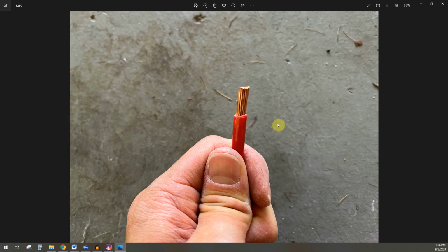And the reason for this is that if you need to take out the wiring later and need to bend it, and you have nicks on the wire, there's a chance you can actually break off a piece of stranded copper, and that would not be good. So the goal is you don't want to do that, because when I think about it, when you put the lug on this and torque it down, it's going to tear the crap out of the copper. So basically try not to make nicks. That way, if you do need to redo it later, you won't break a piece off down here. So that's why you don't want nicks, because there's that chance down the road.